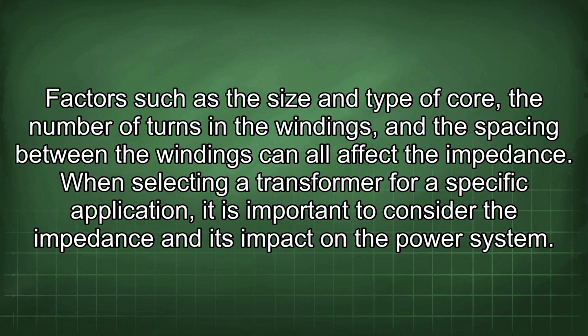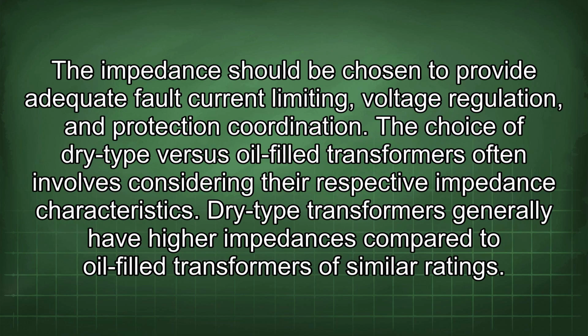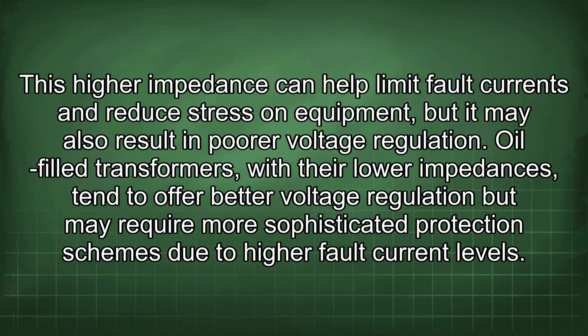When selecting a transformer for a specific application, it is important to consider the impedance and its impact on the power system. The impedance should be chosen to provide adequate fault current limiting, voltage regulation, and protection coordination. The choice of dry type versus oil-filled transformers often involves considering their respective impedance characteristics. Dry type transformers generally have higher impedances compared to oil-filled transformers of similar ratings. This higher impedance can help limit fault currents and reduce stress on equipment, but it may also result in poor voltage regulation. Oil-filled transformers, with their lower impedances, tend to offer better voltage regulation, but may require more sophisticated protection schemes due to higher fault current levels.